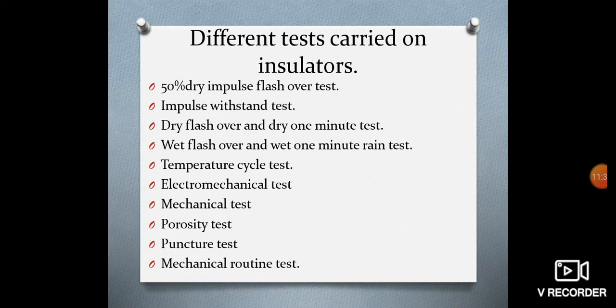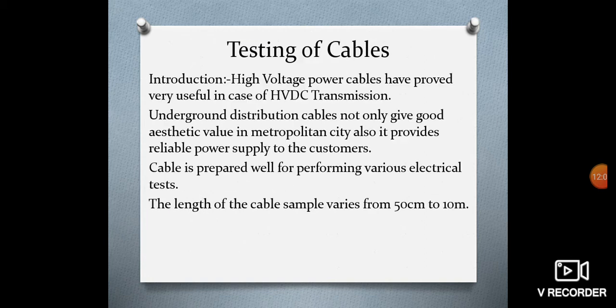Then we have the mechanical routine tests. The string insulator is suspended vertically or horizontally and a tensile load 20% in excess of the maximum specified working load is applied for 1 minute, and no damage to the string should occur. So these are the different tests carried out on the insulator, and now we'll understand the testing of cables.